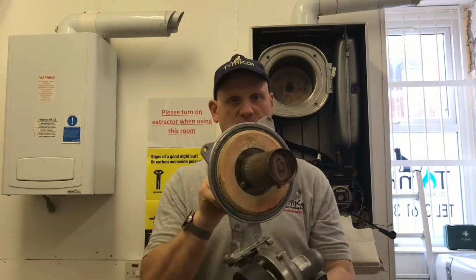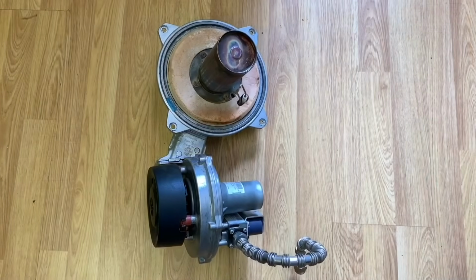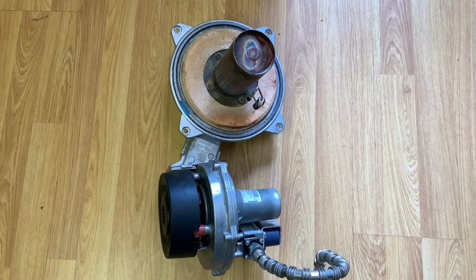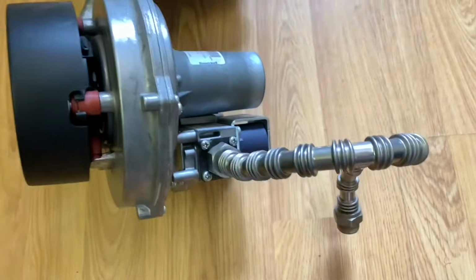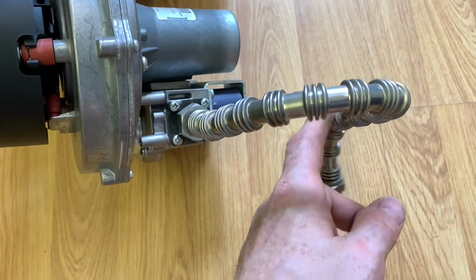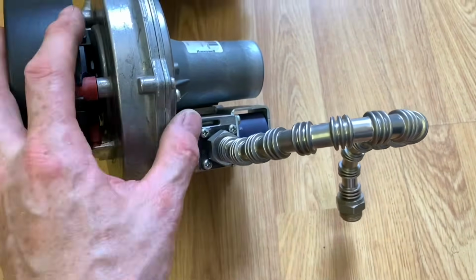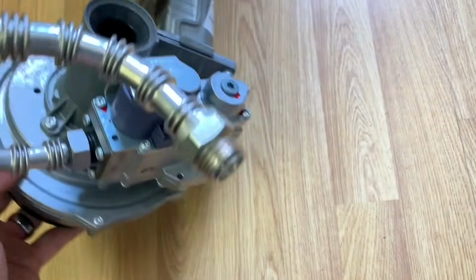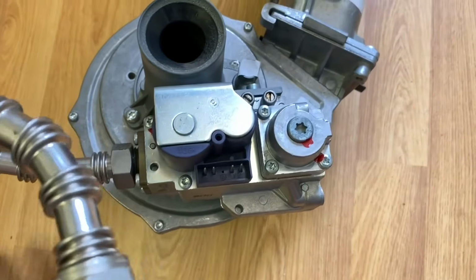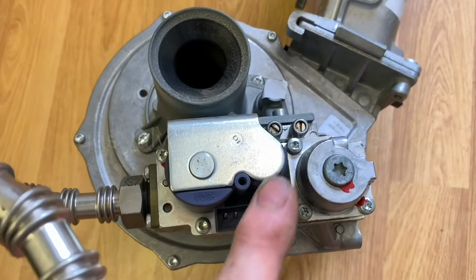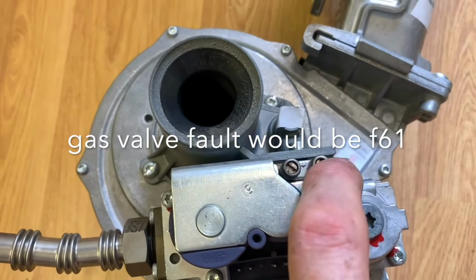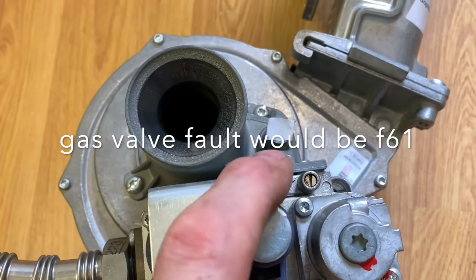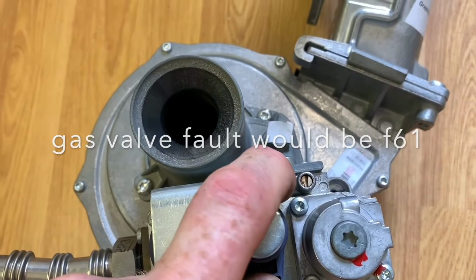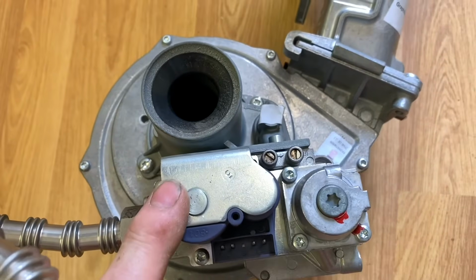So let's have a closer look at this burner now. Now let's have a look at this heat engine more closely. So now you can see the gas pipe where it came in, and it goes onto the back of the gas valve. So you can now see the gas valve more closely. So these are the test points here. One of them is the inlet test point, which is this one down the bottom here, and this will tell us our inlet test pressure.